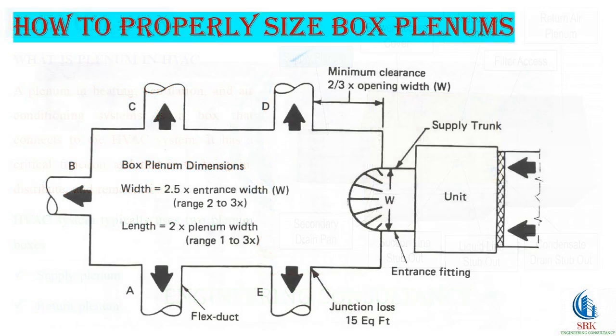A box plenum is a wide but short-length duct used to supply conditioned air to multiple branch ducts. The branch runouts may be insulated flexible ducts or insulated round sheet metal pipes. The box plenum is frequently the principal supply plenum for a small residence, but may also be used in sub-circuits of larger distribution systems.